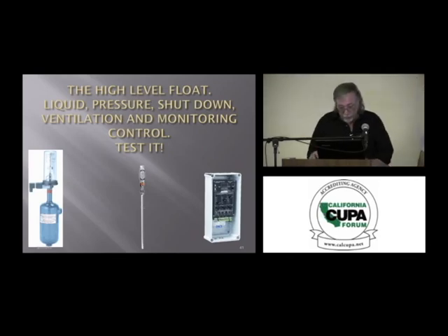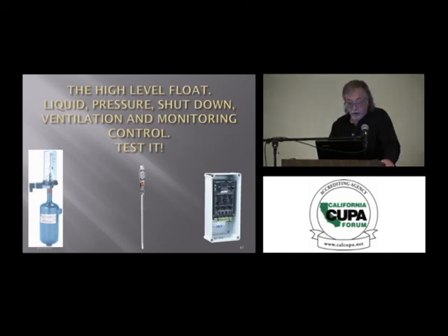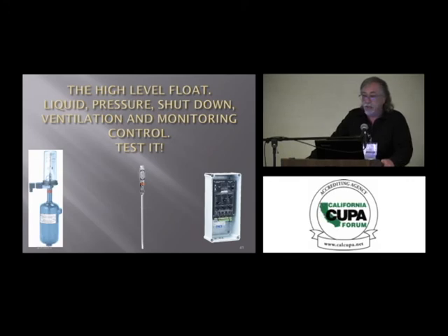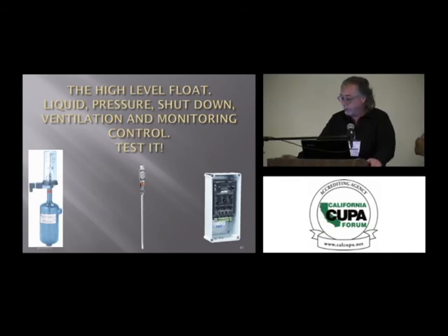Another thing that a big failure in our industry is to annually test our safeties and calibrate our safeties and our controls. And the same goes when they're starting a plant or after modifying a plant. They should have a checklist, and they should be checking all their safeties. If nothing else, they should be checking their high-level cutouts, and typically it's a float, for their compressors to protect the compressors, and they should be checking their high discharge pressure cutouts. So you can't have an overpressure condition. We should never lift a relief valve. Okay, we have other controls in our systems to protect us, high pressure cutouts, etc. The relief valve is the final backup. If a plant is lifting relief valves, they're not testing their safeties.